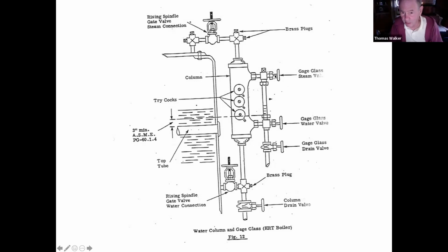Steam has a tendency to blow out or up. So if the gauge glass breaks, close the water valve first. However, after you've replaced the gauge glass, you're going to want to crack the steam valve first to temper or warm up the glass before you put hot water in it. Does everybody kind of get that? I recommend you try to replace a gauge glass once in your career, but after that, don't do it anymore. Get maintenance or somebody that likes to do that to do it. That way you'll figure it out. You'll understand that it's not real complicated.